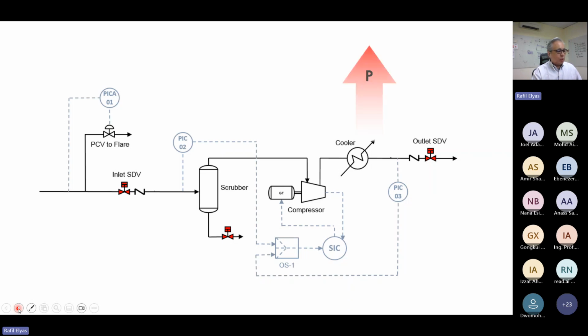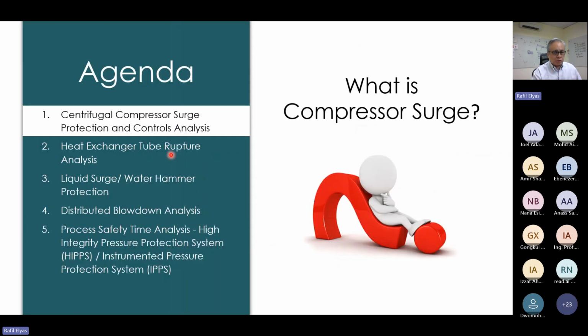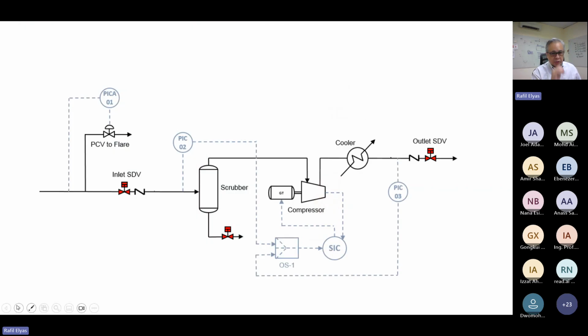Okay, so what do we mean by compressor surge, centrifugal compressor surge? This is just a quick sketch of a typical first stage of a compression system. You can see that it consists of piping, an inlet header, in this case, where you might have a PCV to flare. You've got the inlet scrubber to knock out any liquids, your compressor and driver, aftercooler, outlet SDV, and you normally have a check valve over here to reduce your surge volume.